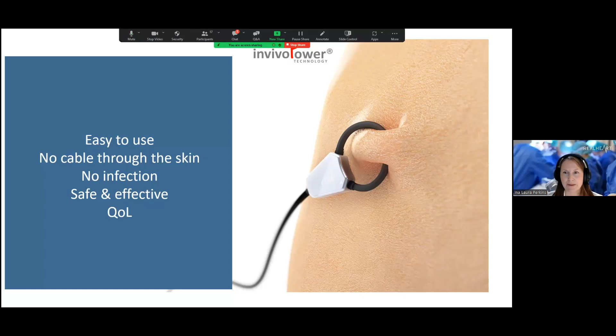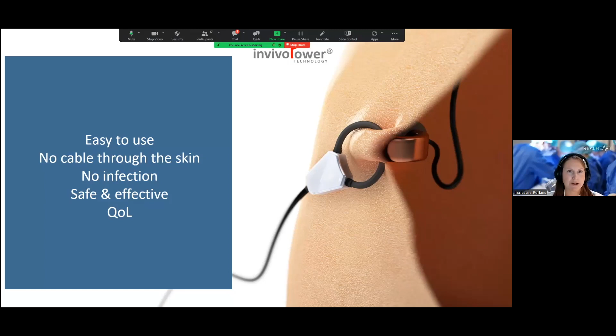Like you have an inner coil and you have the skin, you have the outer coil. If these are not aligned, then you don't have safe energy transfer. And you can also have problems with heating of the skin. So stepping away from that is what invivoPower have done with this piercing technology. Like when people put these rods under the skin, that's what they're doing here, where they're putting the internal coil perpendicular to the skin and then enabling this external coil to connect. And when you have this chain, it is safe. There is never any misalignment, and it will charge the inner battery this way, and then you can disconnect. You could have some time off the cable.